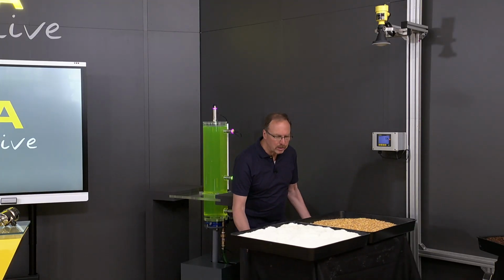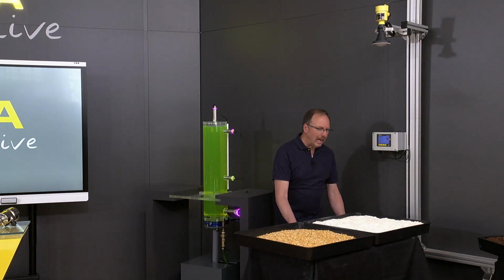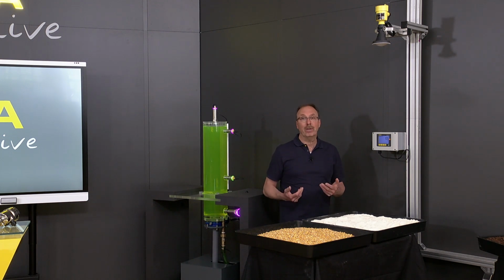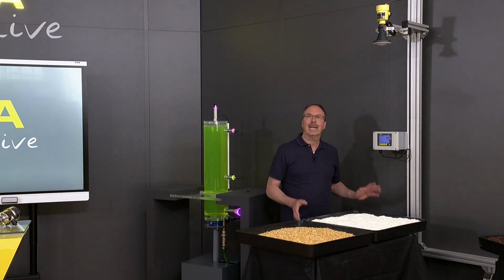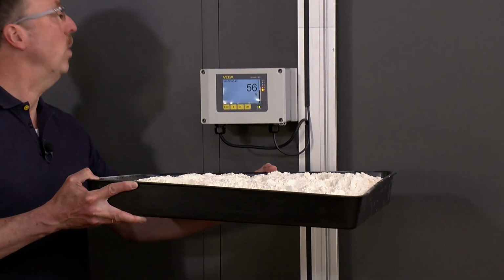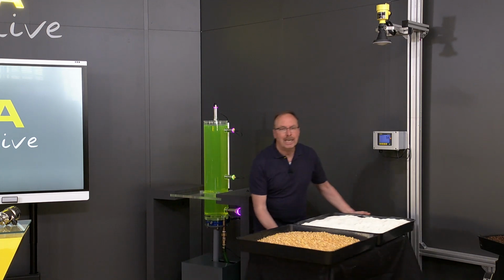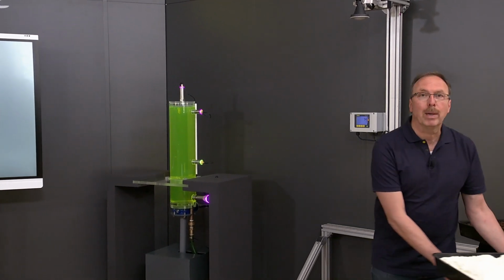After the mill, of course, the corn or the grain looks different, very fine flour. And here, of course, it's not only the reflective conditions of the product which are very low, also the conditions inside of a silo. We have pneumatic filling, a lot of dust, but the microwaves can penetrate the dust, so it's very simple to measure without any influence. So also 56%. I lift this also a little bit up because it's not so heavy. 60%, nearly 70%, depending on the distance. In this kind of application, we need bigger antennas to get better focusing, and therefore we use the VEGA Pulse 6X.